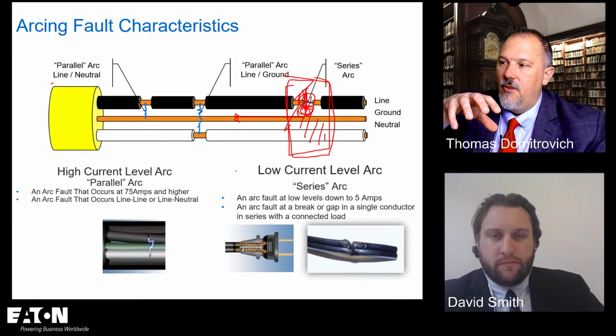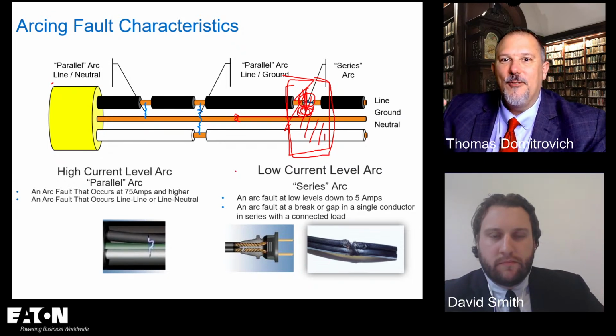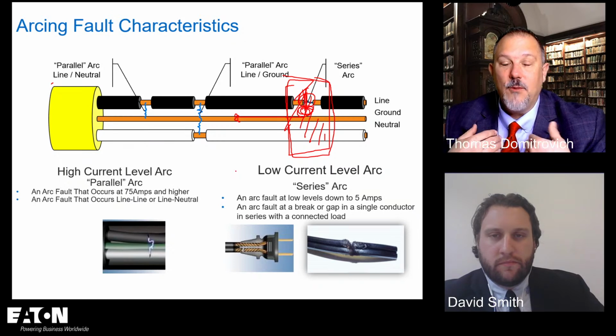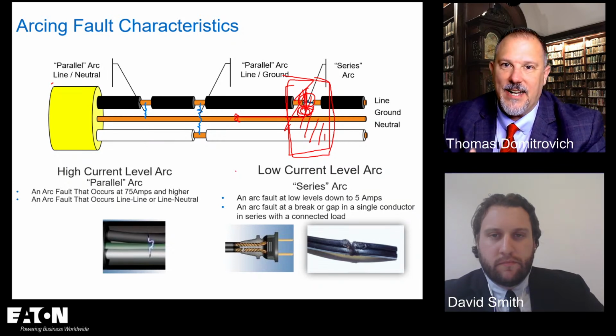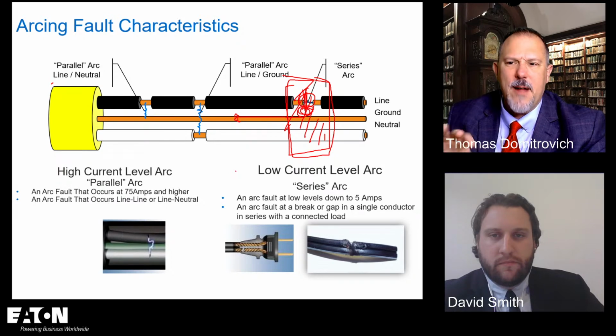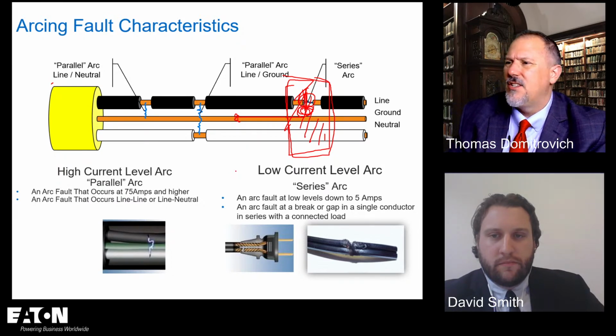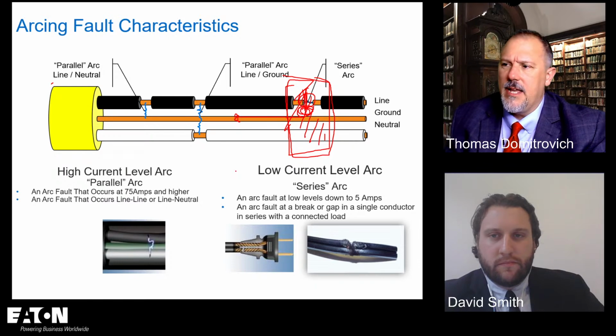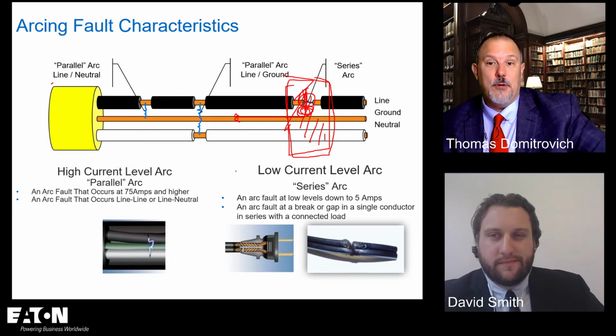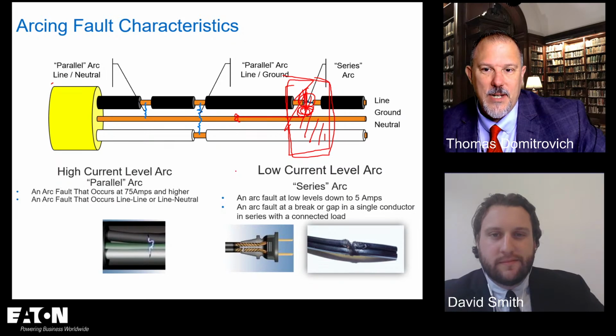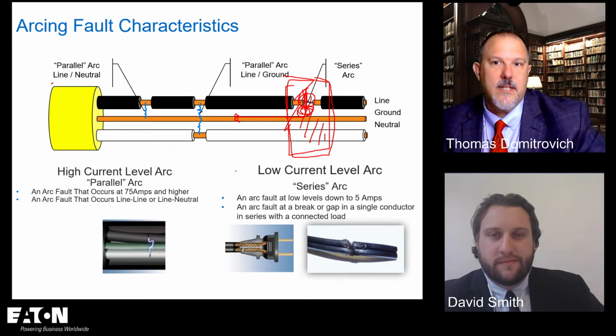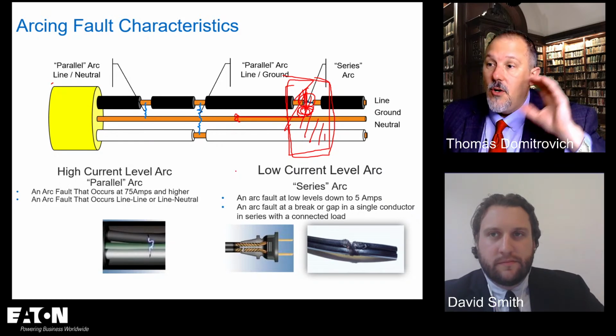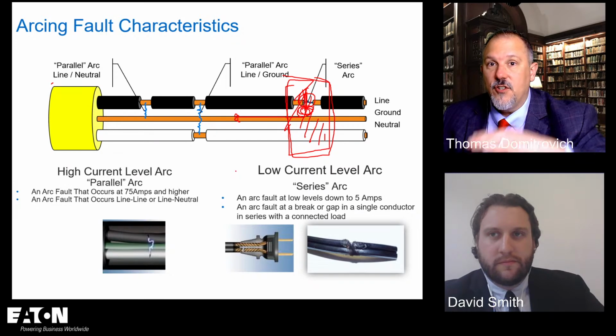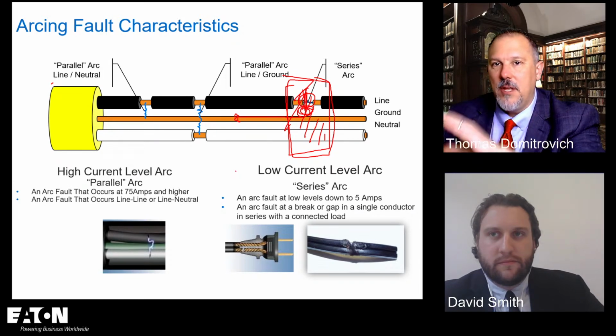And that equipment grounding conductor, the current going outside the path, I would put in all branch feeder AFCIs had ground fault protection of equipment at around 30 milliamps. I think Square D or GE was up around 50 milliamps. We were at 30 because we listed ours to UL 1053. We said, look, if we're going to do it, we're going to list it as a 1053 device. Nobody else did it. Okay. So they all had different trigger points, but that's how we passed this test.